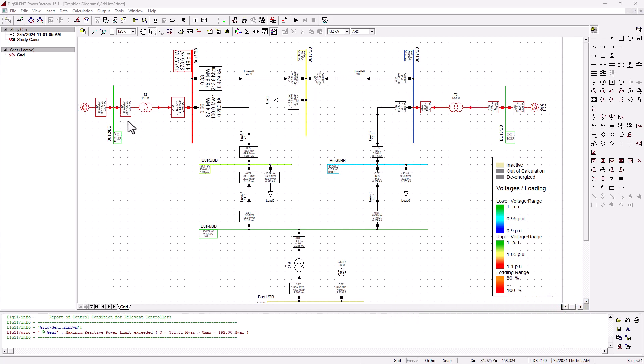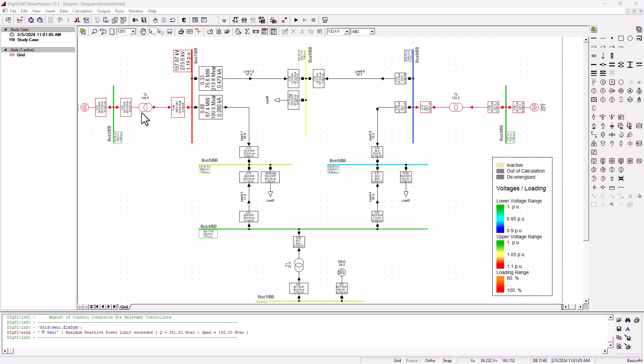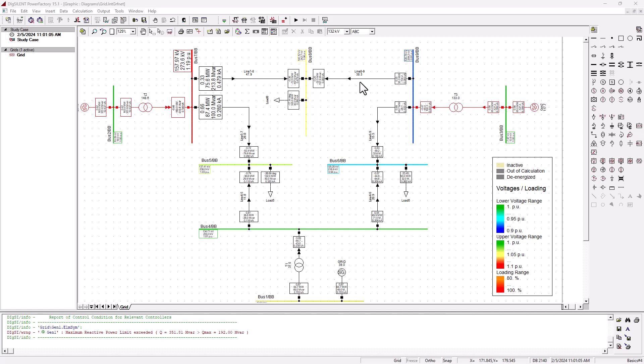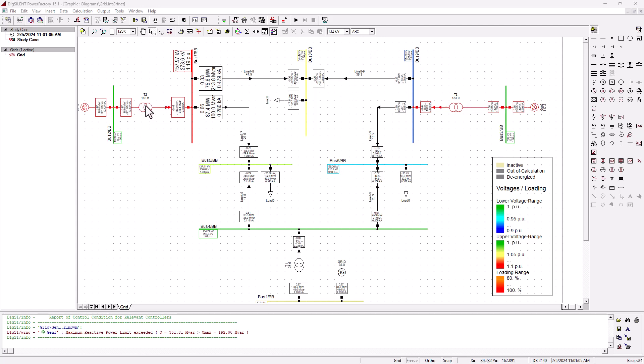Now, you know very well that the best way to solve your overloading problem on the transformers here is to increase your transformer capacity, just as we've done here by increasing the line rating and that makes the overloading go away. As you can see, overloading is below the 80 percent, so it's normal. If you want to do the same thing here, remember it will cost you a lot of money.